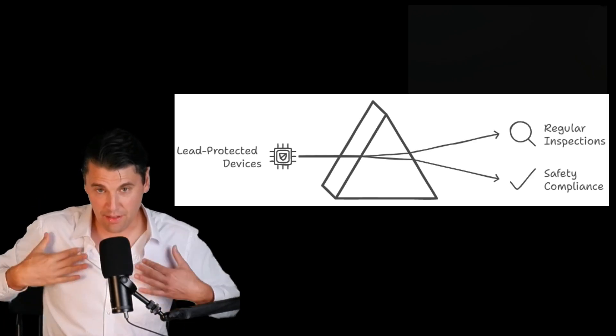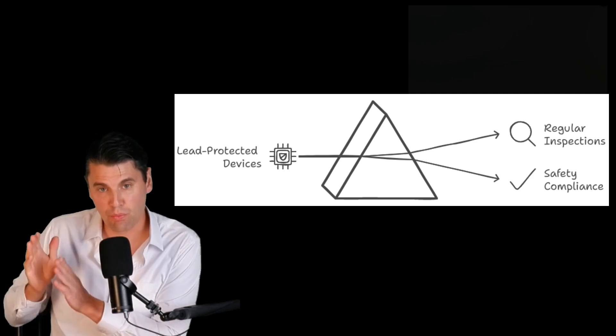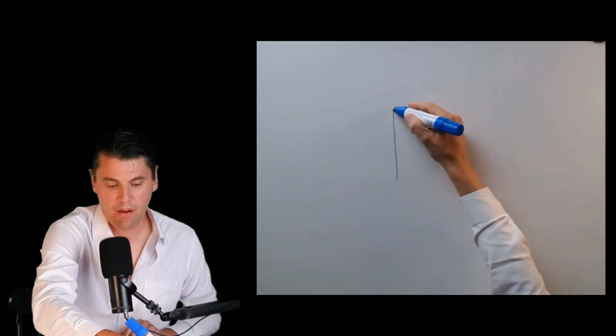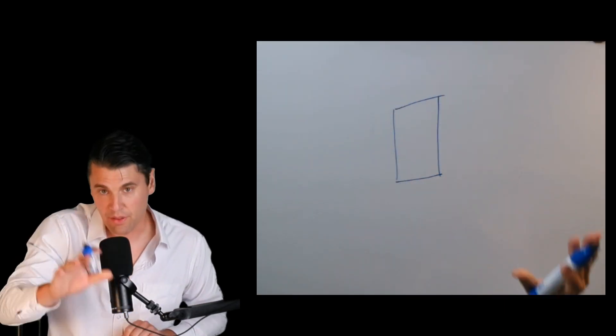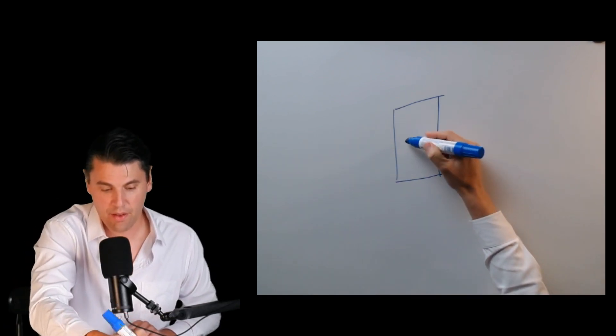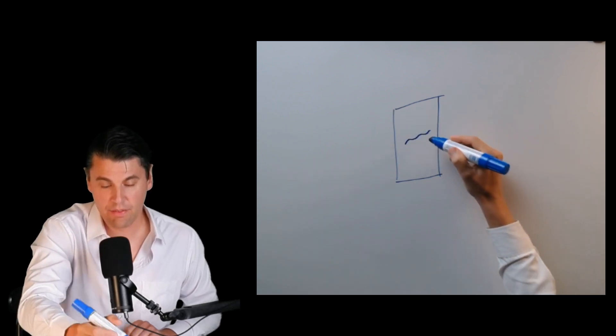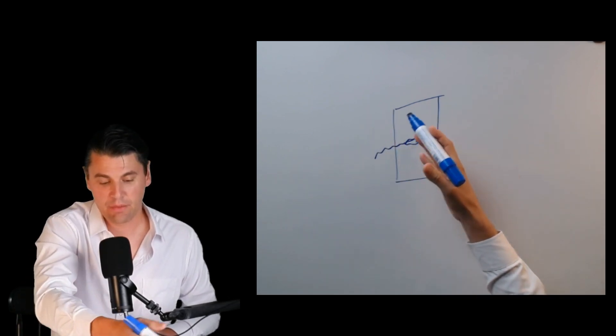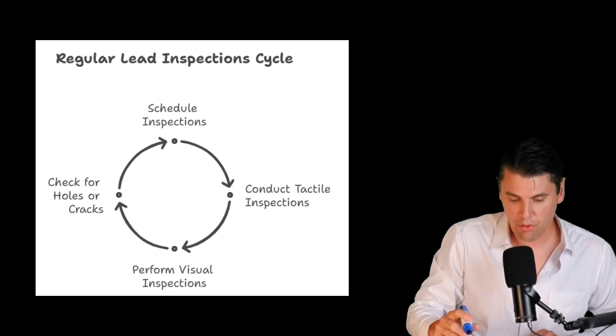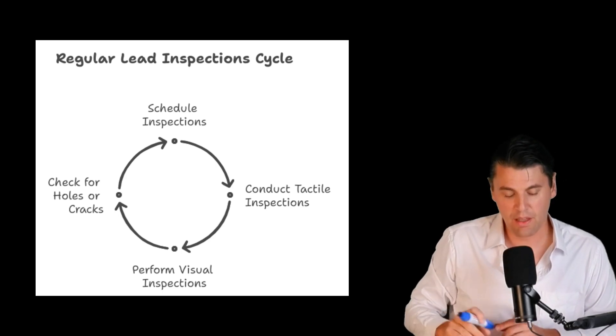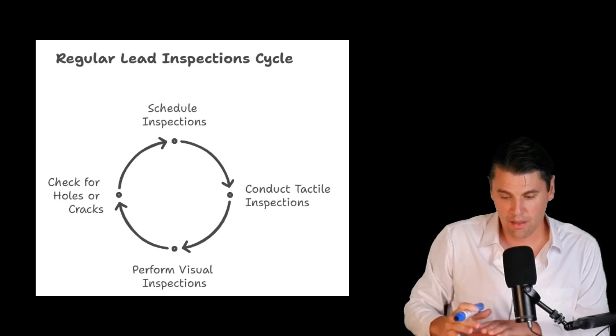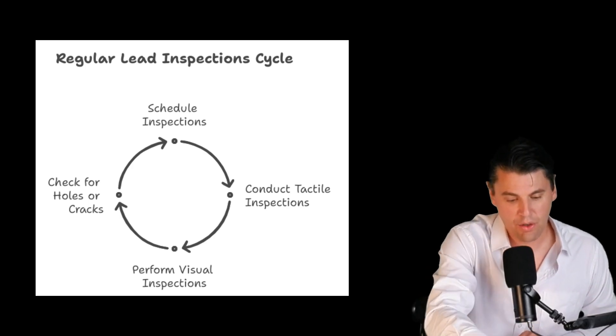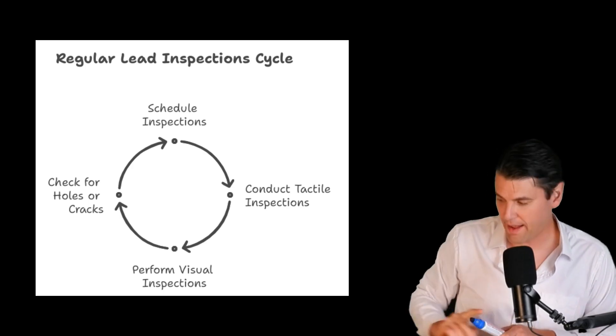Part of dealing with the lead protected devices is also to regularly be doing inspections on those devices. Because if you think about if you had a sheet of lead that was your primary protective device and there was a crack in that sheet of lead or a hole in that sheet of lead, that actually could preferentially let x-rays pass through that crack. You want to regularly be doing inspections of your lead, tactile and visual inspections in order to make sure that you do not have actual holes or cracks within your lead.